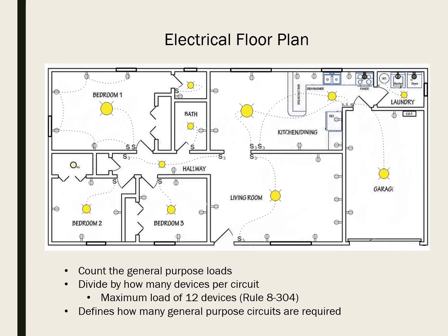At this point, you should know whether or not you're going to be using AFCI breakers or AFCI receptacles, because that's going to change the amount of space available in your panel. An AFCI breaker will take a full breaker spot, whereas if I use an AFCI receptacle, I can use a half breaker spot and then feed my circuit from there. So double check to make sure that you know which way it's going to go.